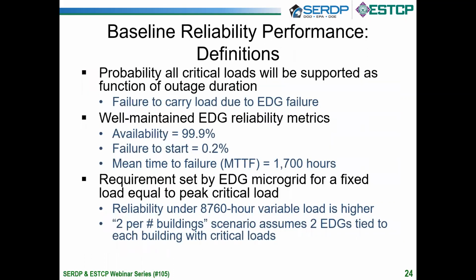So for each installation, we've gone through a calculation to define the reliability metric. The metric ESTCP chose was to define the probability that all critical loads will be supported as a function of outage duration. To set it in other words, I have X amount of critical load, which varies hour by hour through the year. What's the probability that I will be able to supply power to manage 100% of that critical load?